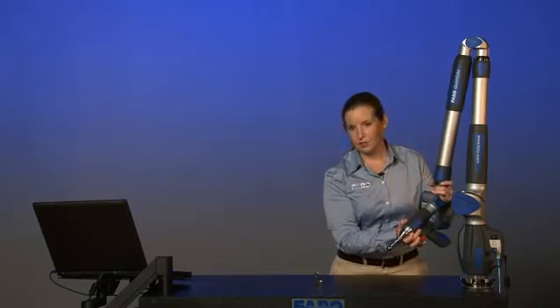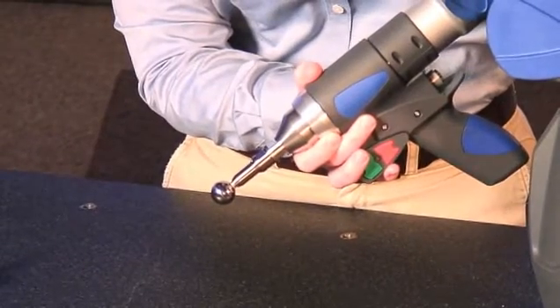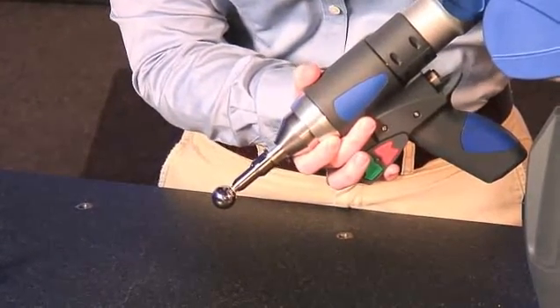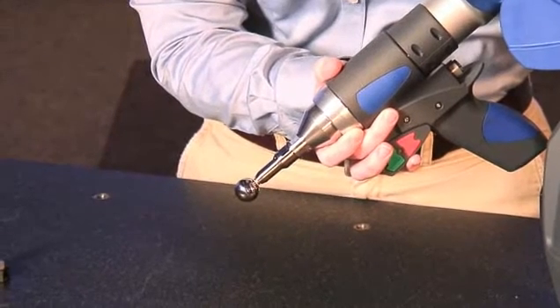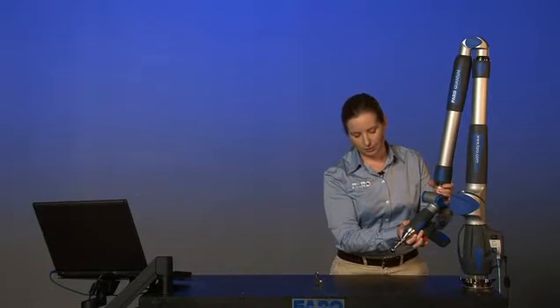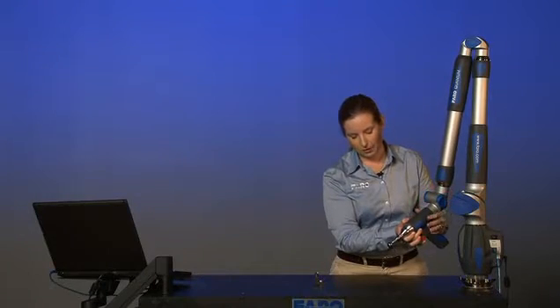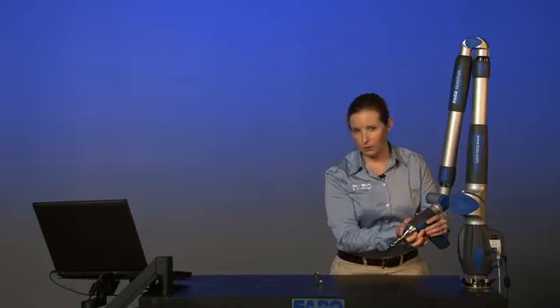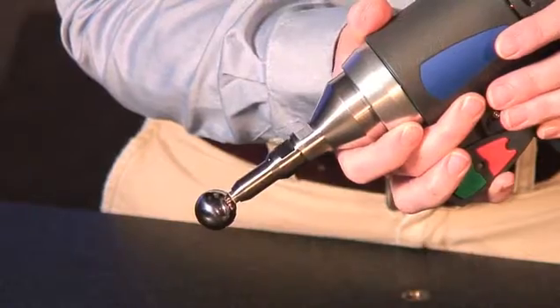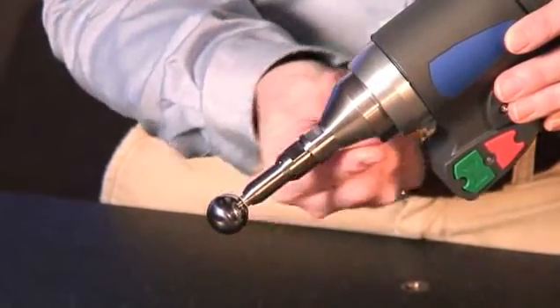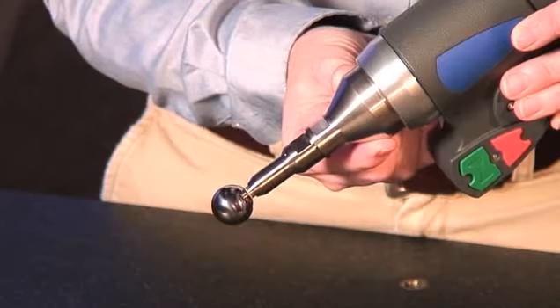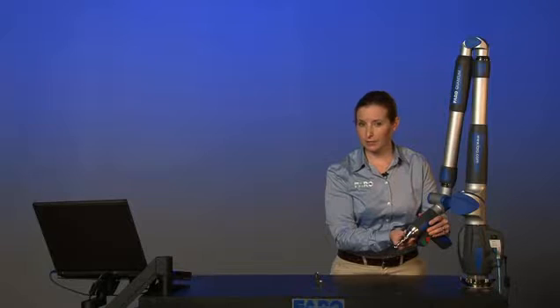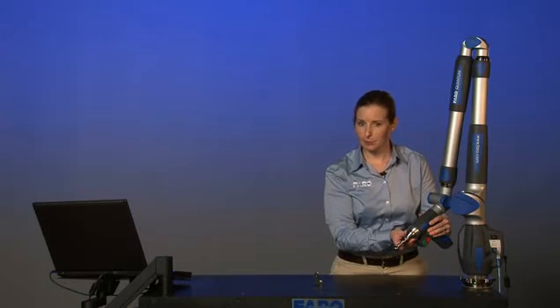What we have attached to the end of the arm here is a 20-millimeter ball probe. This particular probe is a custom probe created for a specific measurement in which a larger ball was required. This 20-millimeter ball probe is attached to the end of the arm, and now we're going to define it in the software and then calibrate it.